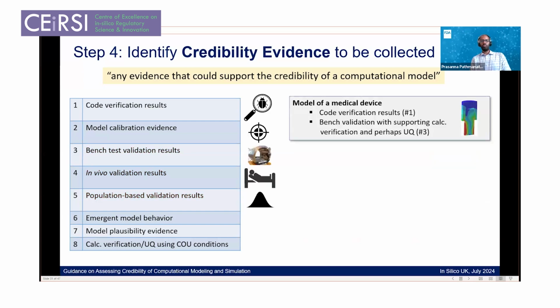So in terms of what should be submitted, we don't provide any specific recommendations. We don't say that, always submit this for this case or anything like that. But we emphasize that verification results should generally be submitted and some validation results should generally be submitted. And what validation will be submitted will likely depend on how the model is going to be used.